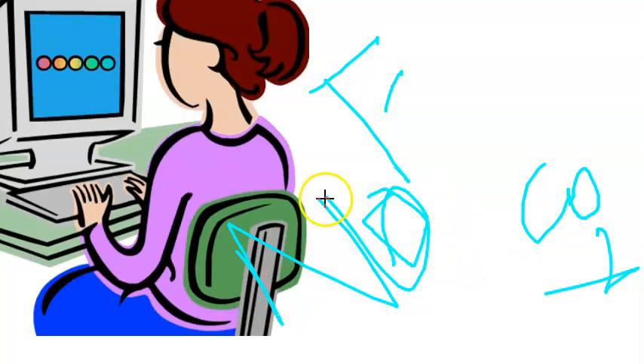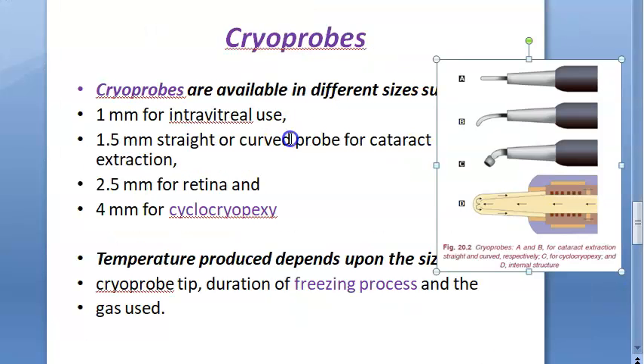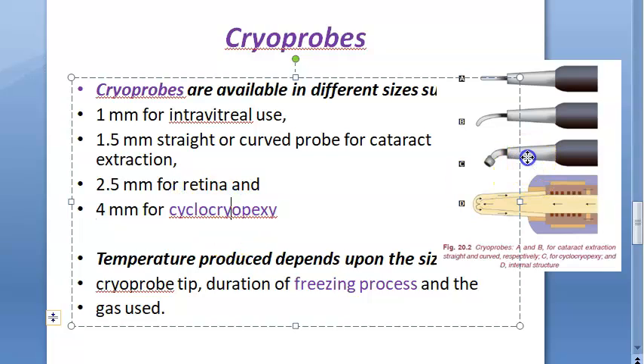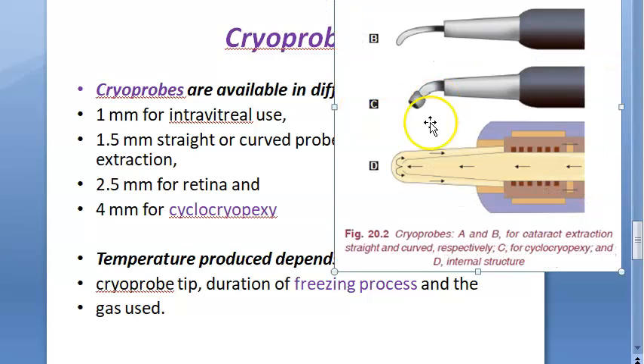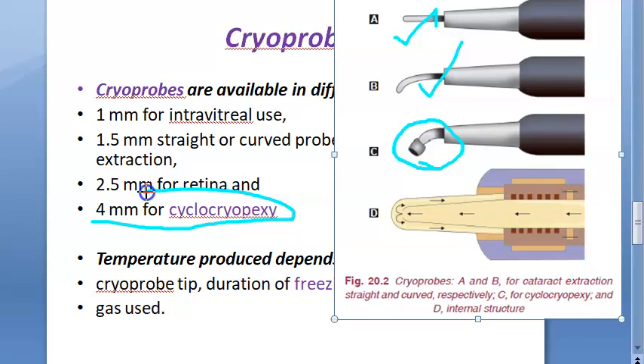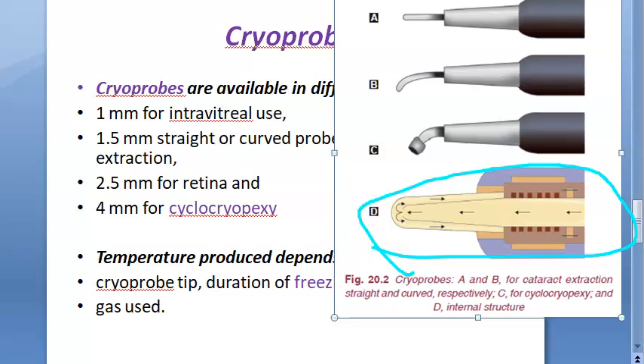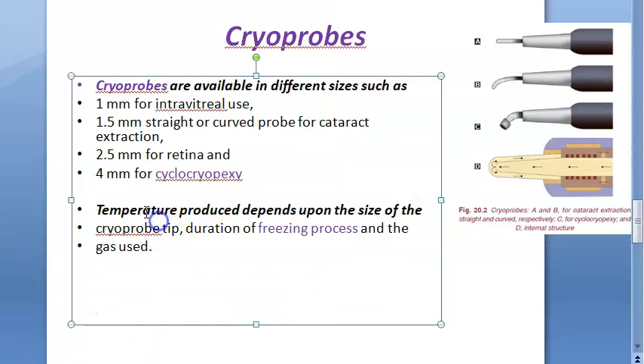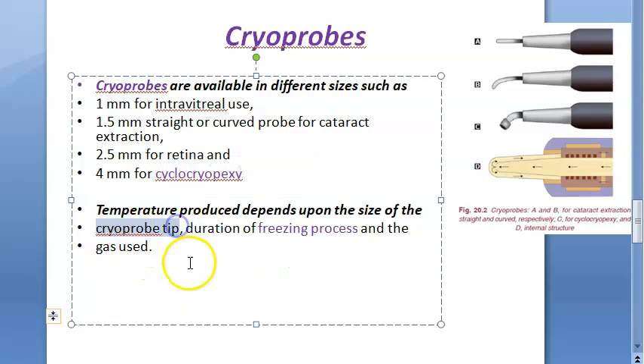There are many types of cryo probes of different sizes: 1 millimeter for intravitreal use, 1.5 millimeter straight or curved probe for cataract extraction, 2.5 millimeter for retinal use, and 4 millimeter for cyclocryopexy. The temperature produced depends on the size of the cryo probe tip, the duration of the freezing process, and the gas used.